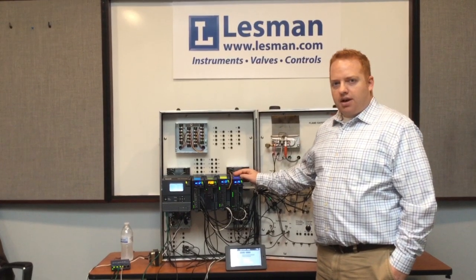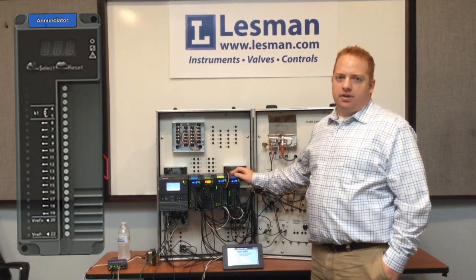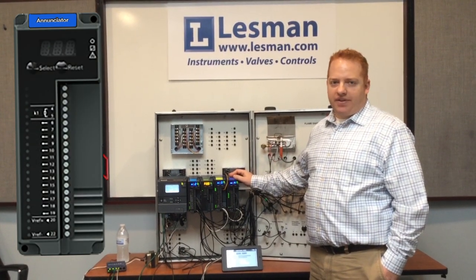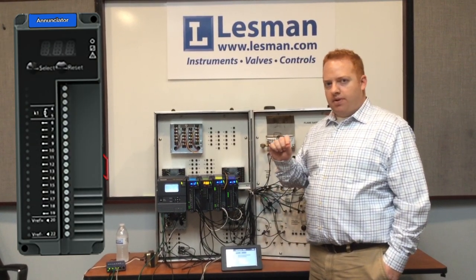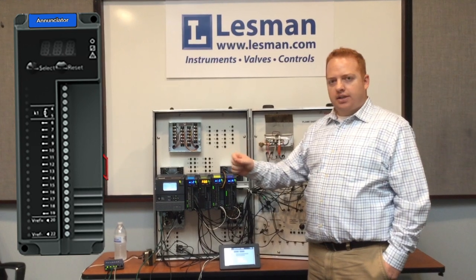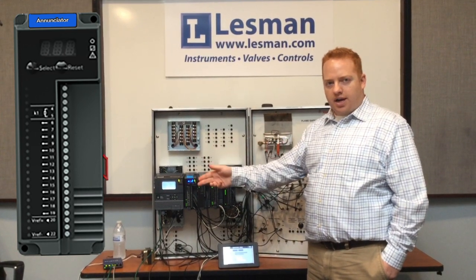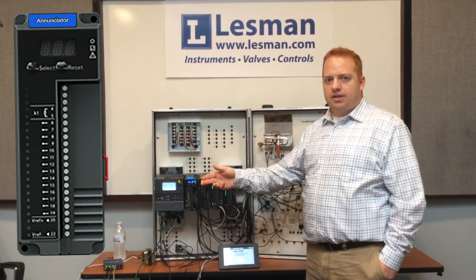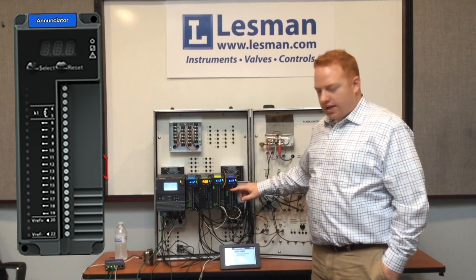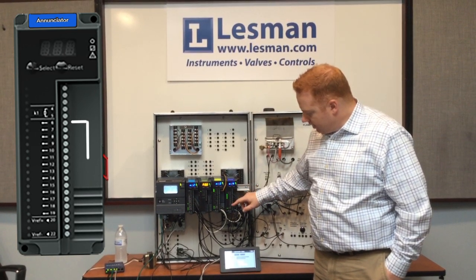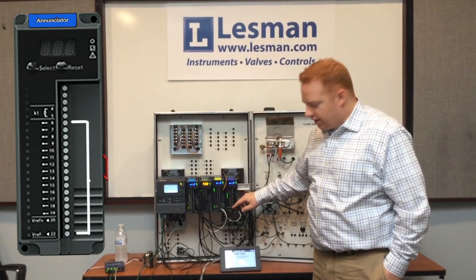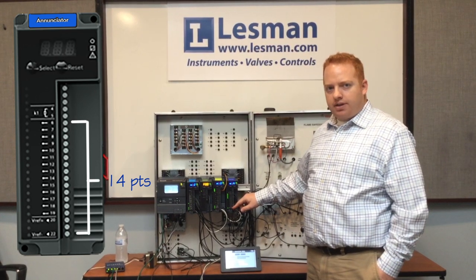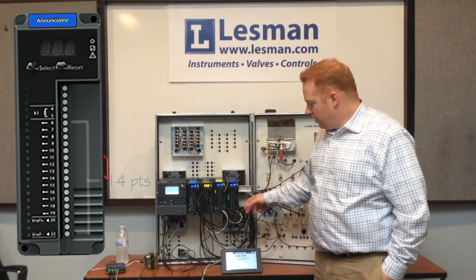The Annunciator Module acts similar to the legacy Honeywell product, the S7830. You would hook up in between all of your interlocks and your interlock string another wire tying back to the Annunciator, and that's represented here by the terminals 6 through 19. So you actually have 14 different points that you can incorporate into the Annunciator.